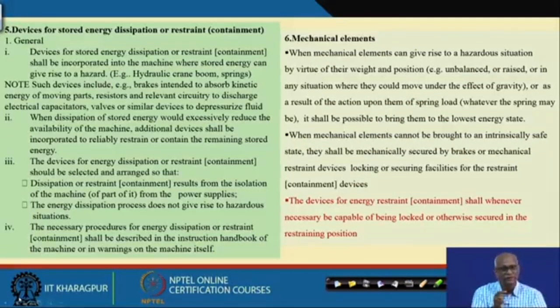Devices for stored energy dissipation shall be incorporated into the machine where stored energy can give rise to a hazard. Such devices include brakes which absorb energy, and resistors. Sometimes you cannot dissipate, because dissipating the energy would take a lot of time for restarting. Then you should have separate devices. Without dissipation, how could you hold the component in position? You should put separate devices, but normally we avoid it.